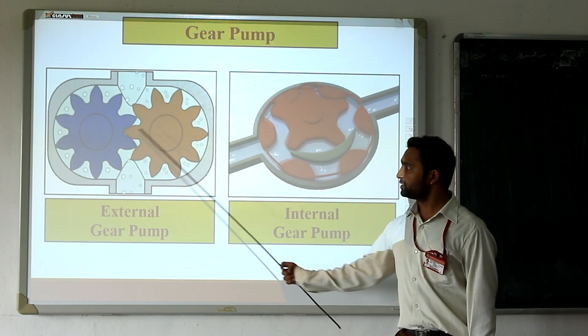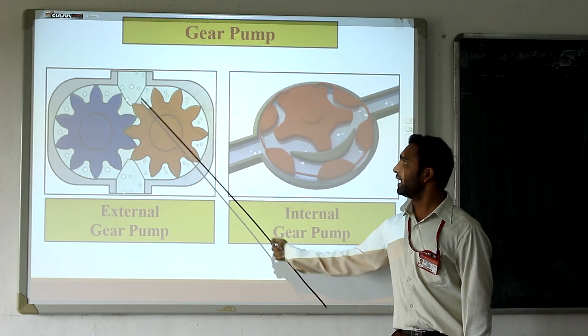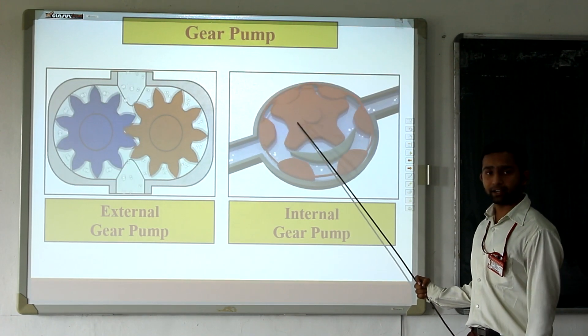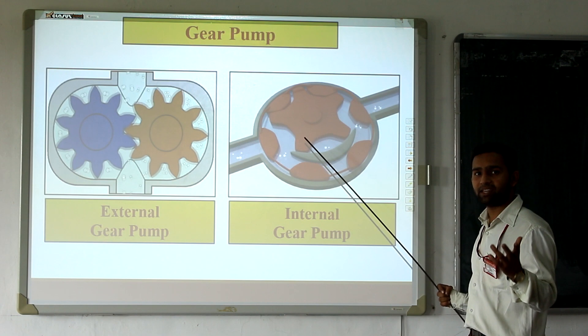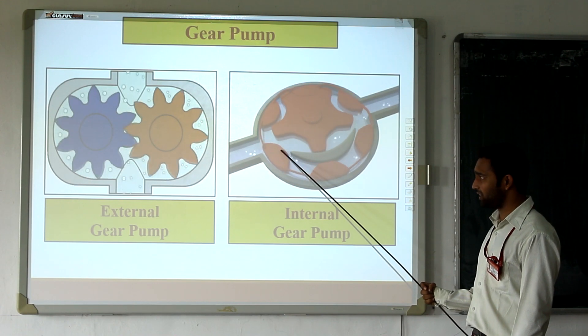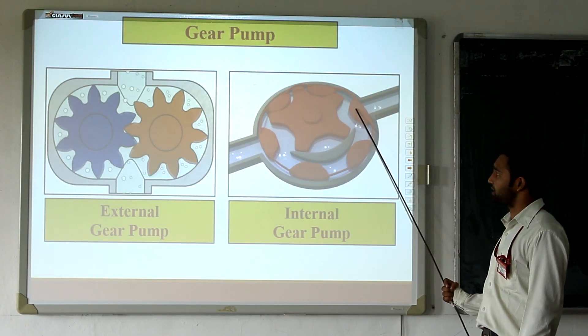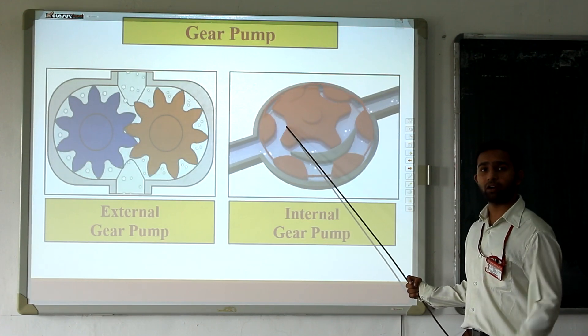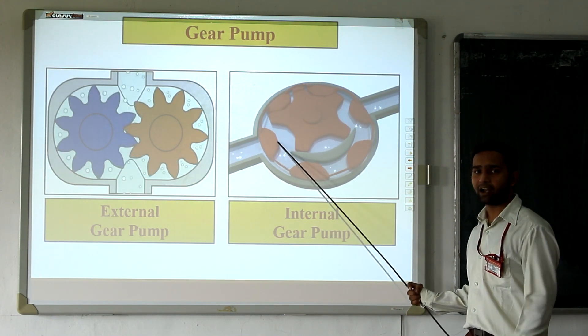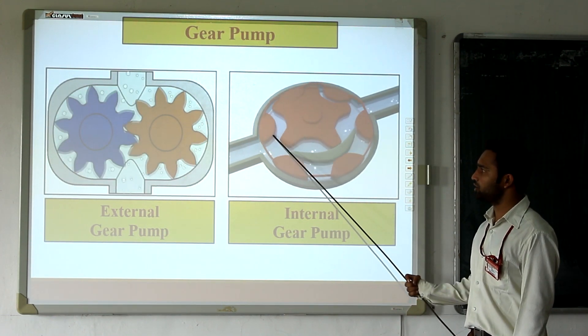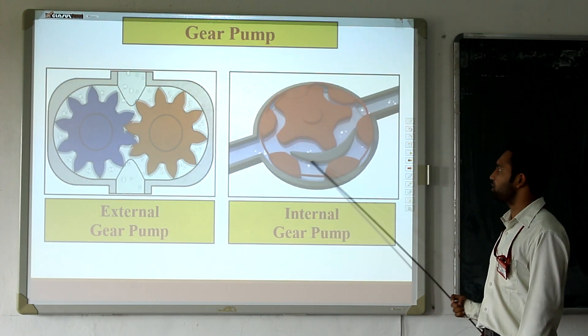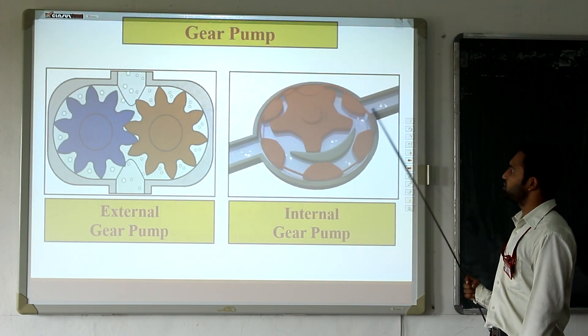In case of the external gear pump, whenever the two gears mesh, discharge is possible, and when the gears are out of mesh, suction is possible. Similarly, in case of the internal gear pump, one rotor and one idler are provided, which creates two regions — one is a lower pressure region at the suction side and one is a higher pressure region at the discharge side. Whenever gears are in mesh, that generates discharge, and when gears are out of mesh, that indicates suction of fluid.